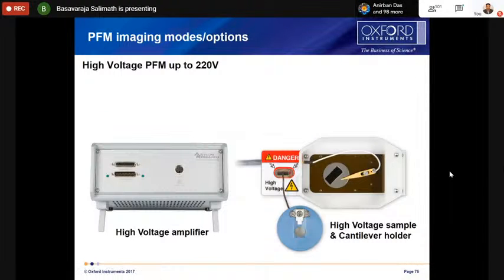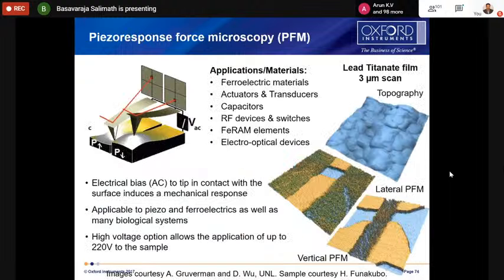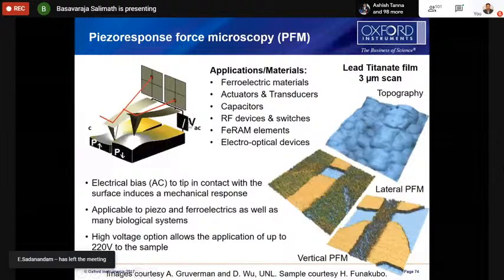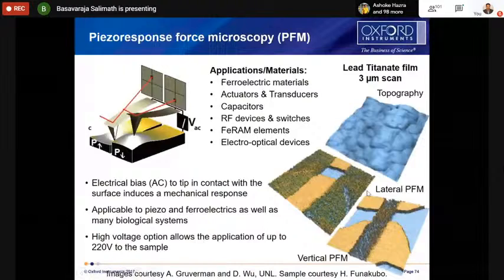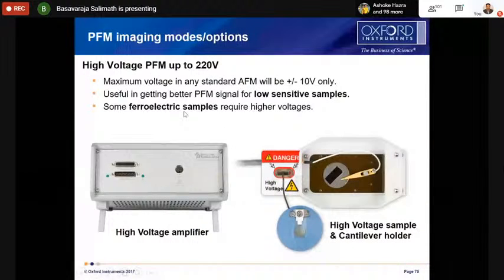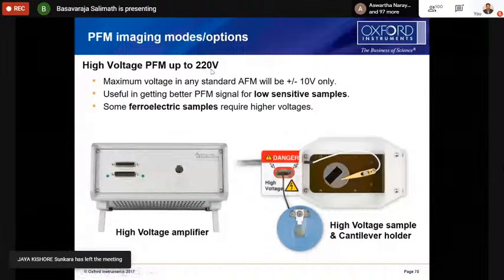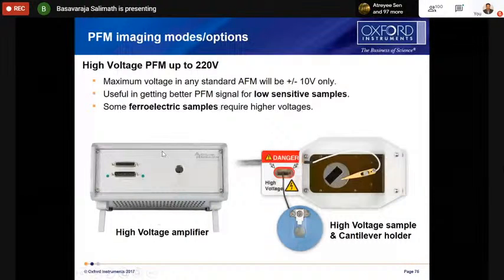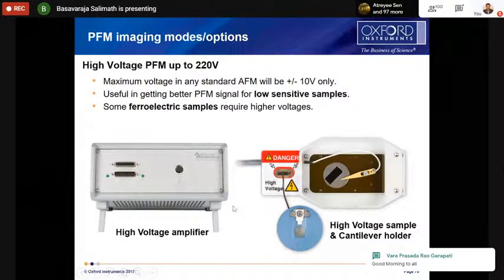Some piezoelectric samples need a higher voltage, whereas with normal AFMs we can apply only 10 volts to the sample. With a high voltage setup, we can go up to 220 volts. Some samples, for example PPLN, require higher voltages. So we have higher voltage setups also.